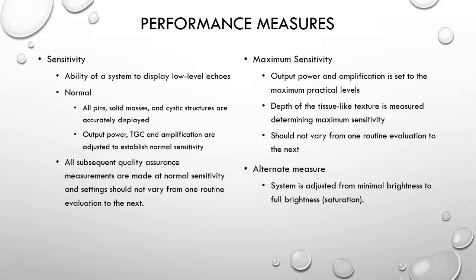So we have some performance measures that we're able to make with our phantoms. One is called sensitivity, and this is the ability of the system to display low-level echoes. When it's normal, then we're able to see all the pin, solid masses and cystic structures displayed on our phantoms. The output power, time gain compensation, and overall amplification need to be adjusted to establish whatever the normal sensitivity is for that machine. And then all subsequent quality assurance measurements are made with the settings at the same location.